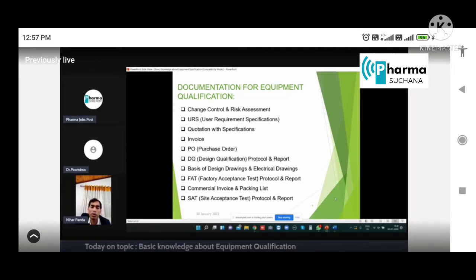Even that FAT protocol can be prepared by the manufacturer also. According to the FAT protocol, the user department should send some person, either an engineering head or a technical person or the user department head. They should travel, they should visit the factory and check the equipment, whether it is ready, whether it is okay as per the design qualification, whether it is manufactured or constructed as per the DQ, and whether it is working as per the expectations. They have to verify. They can even go for a trial batch in the FAT.